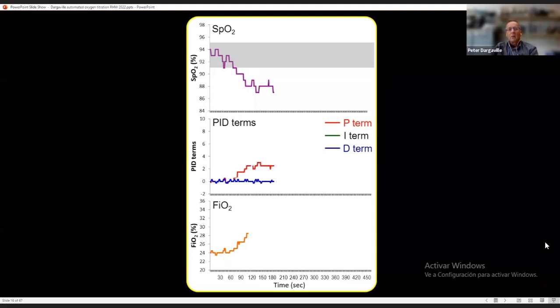And then what now needs to happen is that the algorithm has to be able to cope with what's called steady state error. And so we've made an initial change to FiO2, but now the SpO2 is stable but below the target range. And the P term won't be now changing. And so we'll be relying on the I term, showing accumulated past errors that will continue to ramp up. And as a result, the FiO2 will continue to ramp up to resolve this hypoxic event.